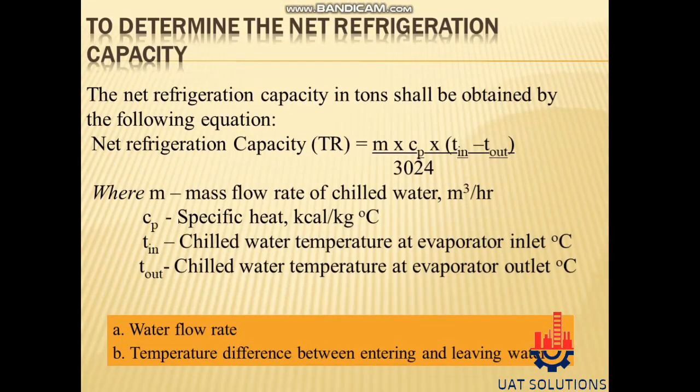To determine the net refrigeration capacity, the net refrigeration capacity in tons shall be obtained by the following equation: Net refrigeration capacity in TR equals M × CP × (T_in − T_out) divided by 3024. Where M is mass flow rate of chilled water in cubic meters per hour, CP is specific heat in kilocalories per kilogram °C, T_in is chilled water temperature at evaporator inlet in °C, and T_out is chilled water temperature at evaporator outlet in °C.